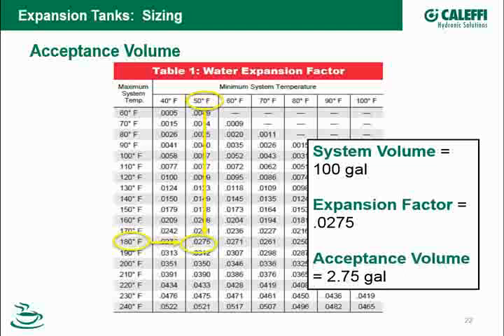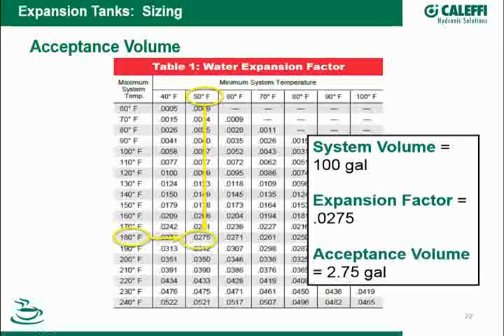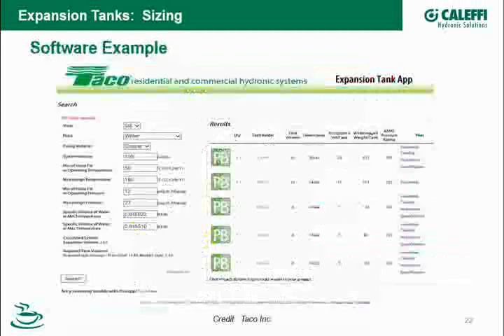If I was going through to do a calculation, and I'm trying to stay away from calculations today, that 2.75 gallons represents 36% of the total tank volume. So I'd have to work the calculation to get the total tank volume. Now, I'm actually today going to take the simpler route. There's a lot of great resources out there for tank sizing. TACO has a software package where I can go through, enter the exact information that we talked about, and come up with a tank size.